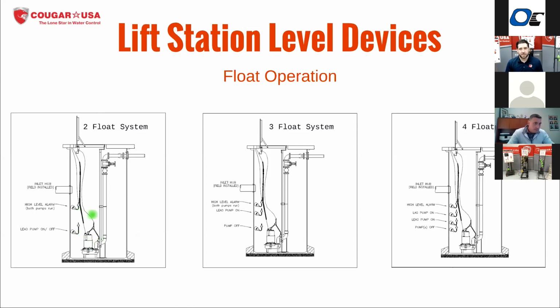You could use it for a sanitary station because you're going to get that alarm when your lag pump comes on, with less things in the pit. So there are some advantages to going with a two float system. A three float system here is going to be a little bit more popular, especially for sanitary applications.